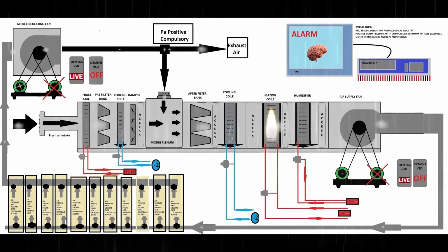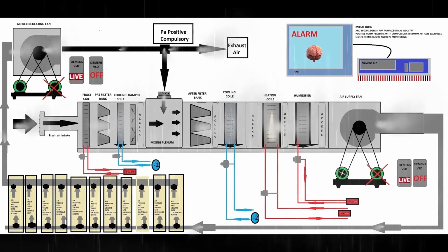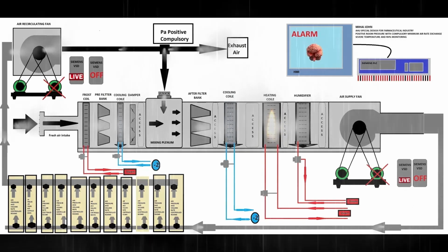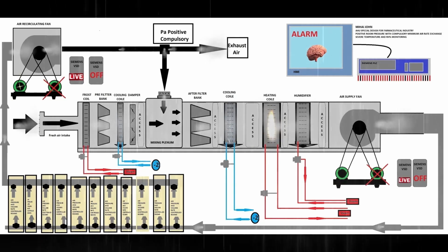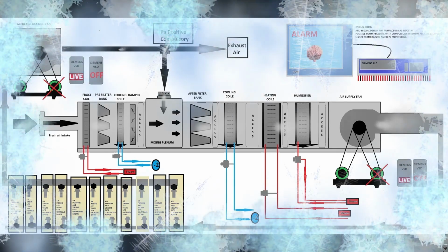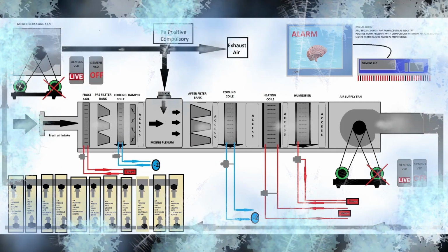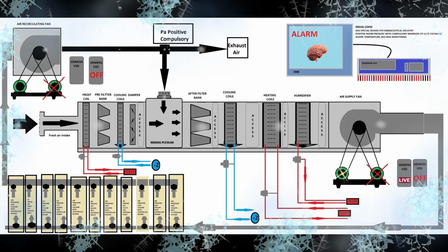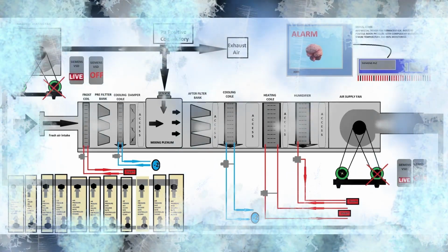Then you will reach the second cooling coil, where you lose more moisture but the temperature will drop. So to overcome the drop in temperature, I'm using the heating coil as well at the same time as the cooling coil. If outside gets very cold, then I'm going to start the defrost coil and the heating coil to keep the air warm.